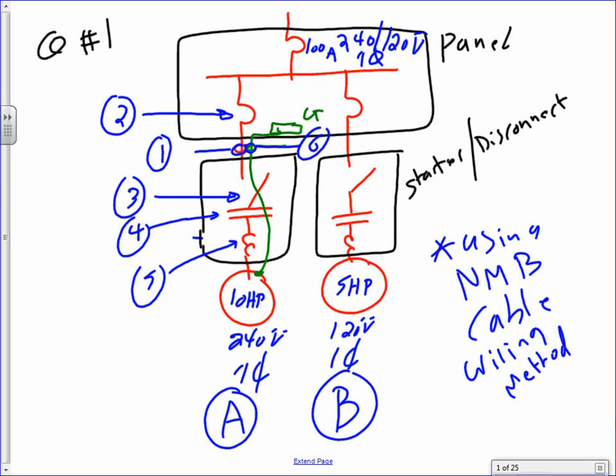You still have 2 chances of getting it when we go to the commercial and industrial, where we'll be doing 3-phase. So what I picked, guys, is 2 pumps or fans. These could be exhaust fans, they're big for exhaust fans, or pumps, motors. It's an A and a B. This one is running at 240 volt, single phase. This one is running at 120, single phase. 10 horsepower, 5 horsepower. They're all coming from a 240, 120 single phase, 100 amp panel.